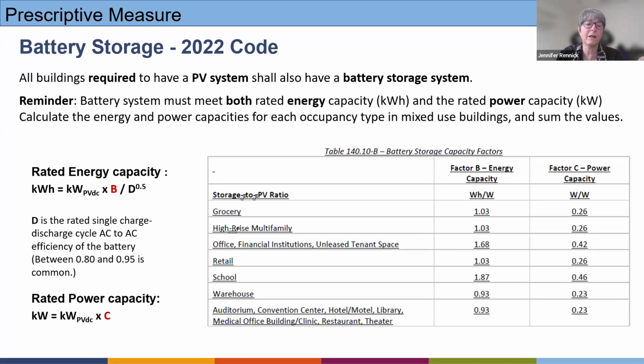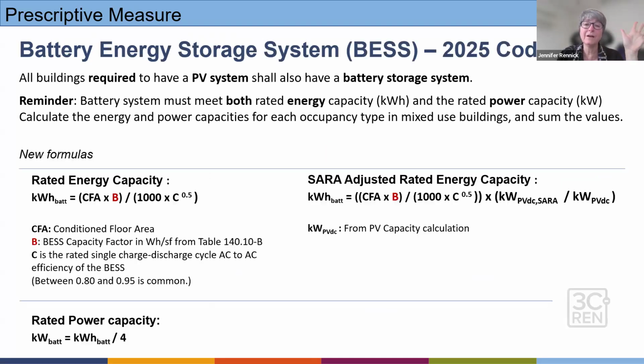And there were two formulas you had to follow, an energy capacity and a power capacity. And probably the trickiest part of the formula is what was called D, the design rated single charge discharge cycle efficiency from AC to AC. That you have to pick up from the manufacturer, but if you want to get a real rough idea, you could use a number between 0.8 and 0.95 for that value, because that's pretty common. And D is to the power of 0.5, or the power of 1/2. And so you would look up these values in this table. Now, under the new code, the formulas have changed.